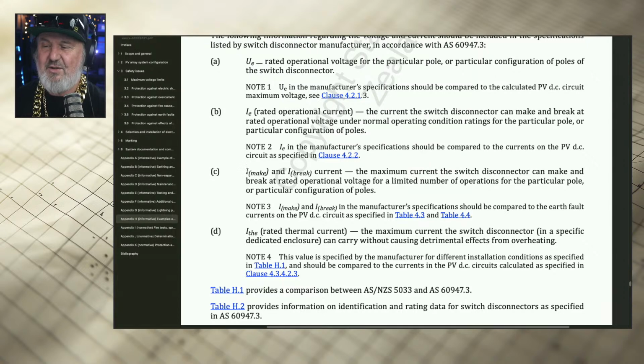And then we've got these interesting ones under Part C. Now, this is kind of the important ones. These were adopted by an amendment to 5033 in 2014, Amendment 2. So it comes from quite a way back, that we realised that switchgear can have a continuous rating, which is relatively low, let's say 20 amps, but it can momentarily interrupt or make, so that's the make or break, a much higher current a few times. So that's known as the ability to operate under fault conditions.